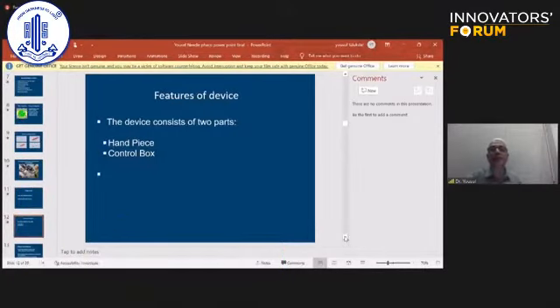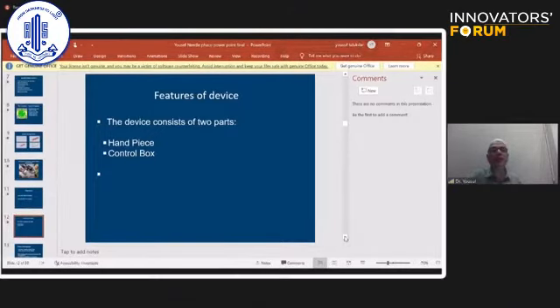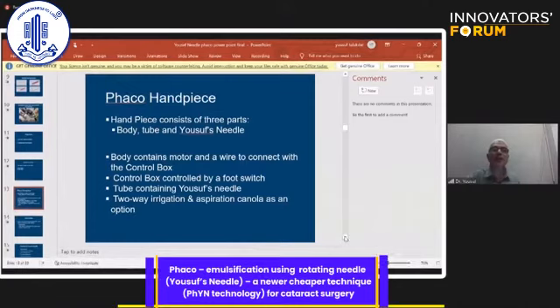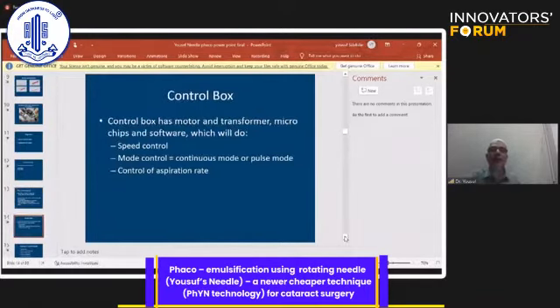Features of the device: this device consists of two parts. One is the handpiece, two is the control box. The Phaco handpiece consists of three parts: body, tube, and YOUSUF needle. The body contains the motor and a wire connected with the control box. The control box is controlled by a foot switch, and the tube contains the YOUSUF needle. The control box has a motor and transformer, microchips, and software, which will do speed control, mode control, and control of aspiration rate.